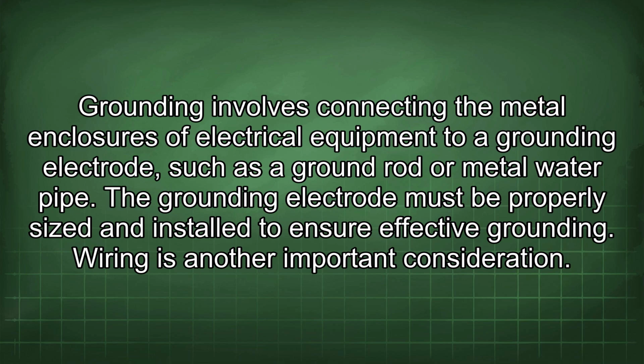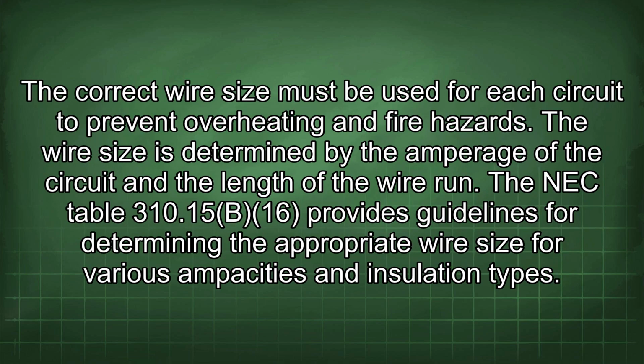Wiring is another important consideration. The correct wire size must be used for each circuit to prevent overheating and fire hazards. The wire size is determined by the amperage of the circuit and the length of the wire run. The NEC Table 310.15(B)(16) provides guidelines for determining the appropriate wire size for various ampacities and insulation types.